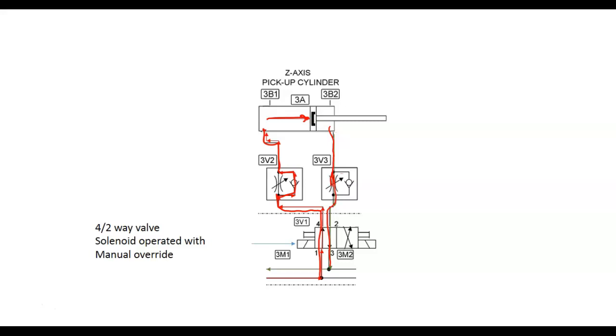A lot of times they'll do it with hydraulics just to set the system the same all the way through. We call this meter out. Meter out is when you meter the exhaust or the return to tank in hydraulics. Meter in is when you control the flow coming in. Normally with pneumatics, we meter out. Now this valve, it's got two positions, and it's got 4 ports. Now, the way they talk about these things, the ports are called ways, because that's different ways that the fluid can flow. So this would be a 2-position, 4-way valve, if you spelled it all the way out.